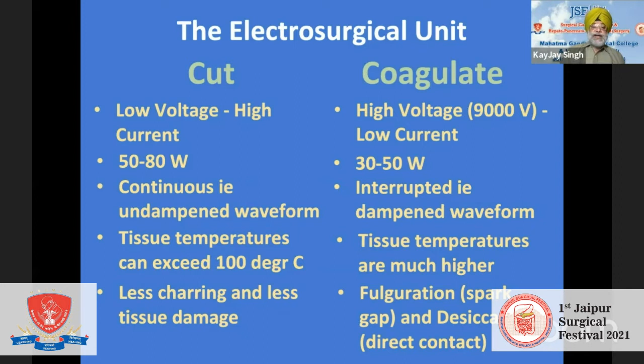Tissue temperatures can exceed 100 degrees centigrade in cut and really very high than this in the coagulation mode. The charring and tissue damage is much less in the cut mode, whereas in the coagulation modes of fulguration, which we call spray, and desiccation, that is direct contact, the charring is much higher. If you see, these are the absolute modes of pure cut and coagulation. The voltage in pure cut is low and the charring is low, and in the coagulation mode the voltage is high, and the charring and tissue damage is also high. You see the cut and the surrounding damage which you see in the coagulation. So we have to be very, very clear what we are using.